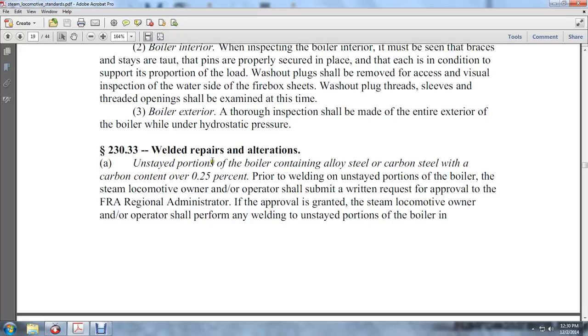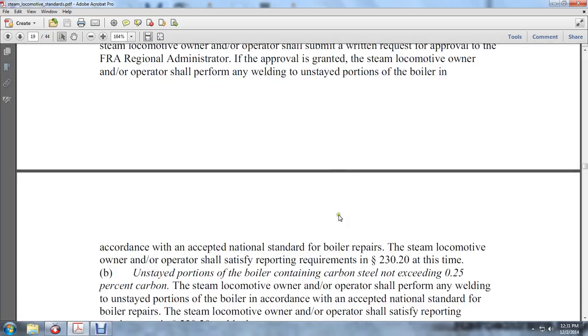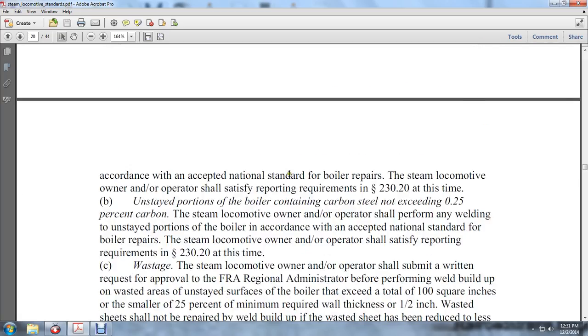Section 230.33 — Welding repairs: For unstayed portions of the boiler containing alloy steels or carbon steels with a carbon content over 0.25 percent, prior to welding, the steam locomotive owner or operator shall submit a written request for approval to the FRA regional administrator. If approval is granted, the steam locomotive owner and operator shall perform the welding of unstayed portions in accordance with accepted national standards for boiler repairs and shall satisfy the reporting requirements of 230.20.